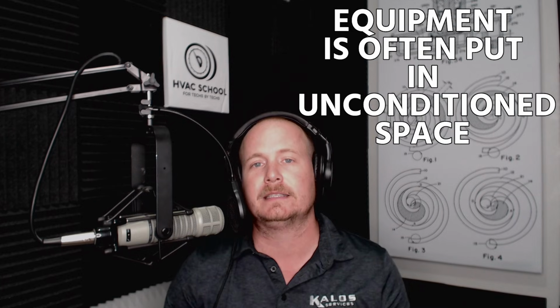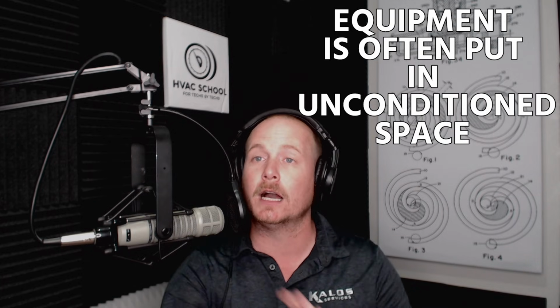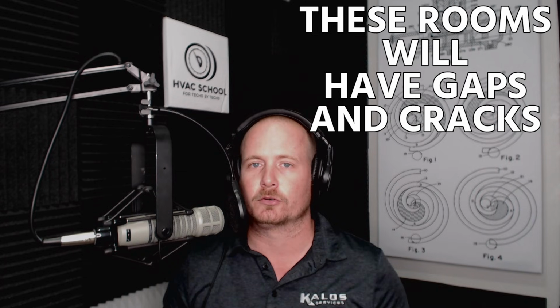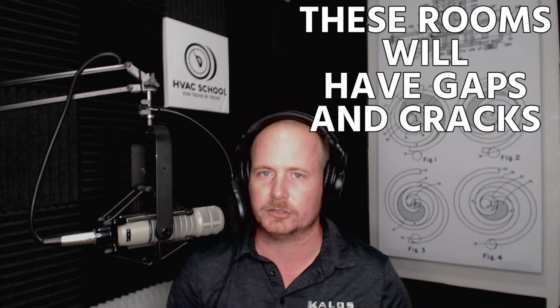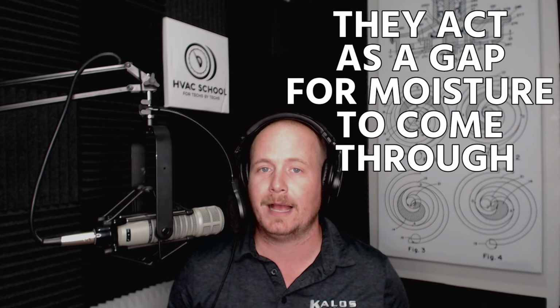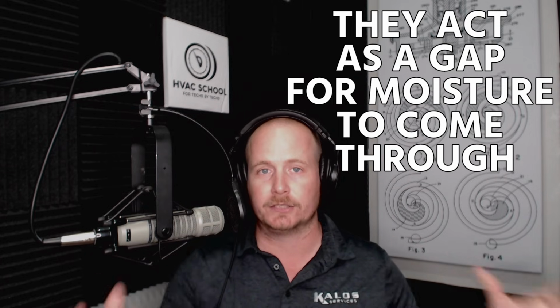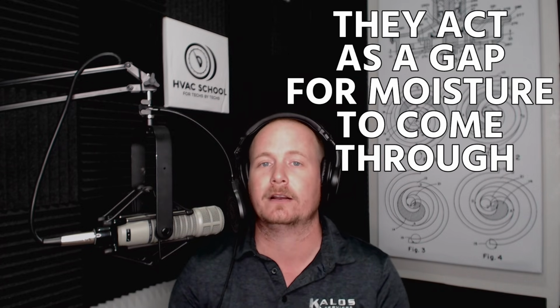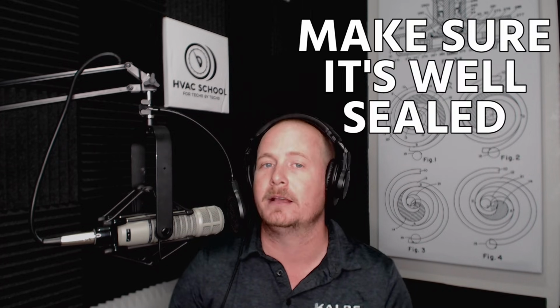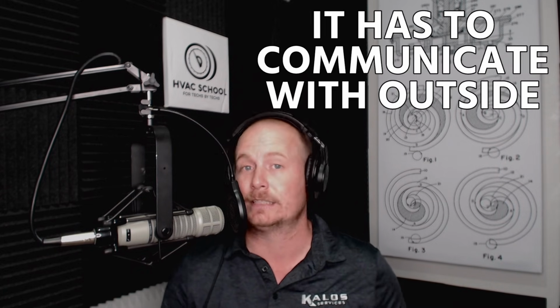A lot of times they'll take this equipment and put it into a closet in an unconditioned space, for example, a closet in a garage, or even a closet in an area that may be conditioned but not kept as well conditioned, maybe a laundry room or something like that. Often these rooms will have gaps and cracks into the attic, or maybe into the crawl space if that's where you are. Those gaps and cracks act as a path for moisture to come up through those spaces. So whenever you're putting an air handler in a closet or something like that, you need to make sure it's well sealed. Now, obviously, if you're installing a furnace, an 80% furnace, that has to communicate with the outside.